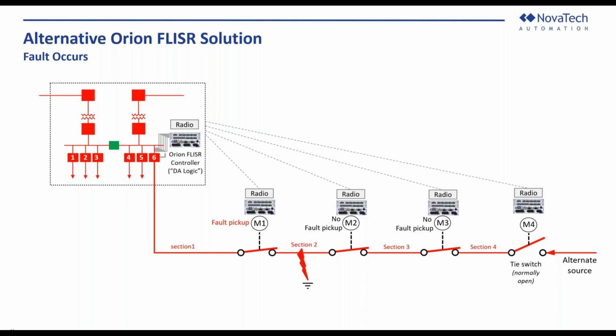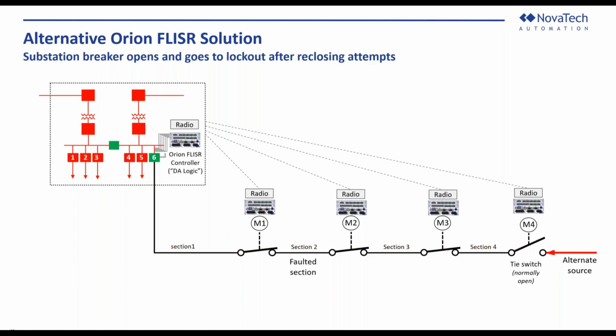M1 will pick up the fault and report it to the FLISR controller, right? In this topology, the fault is picked up only at M1 and not M2 and M3. So we can assume that the fault is probably between M1 and M2. That triggers the substation breaker to open and go to a lockout state after attempting a number of reclosing attempts. Once that is done, we know there's a faulted section, section 2.